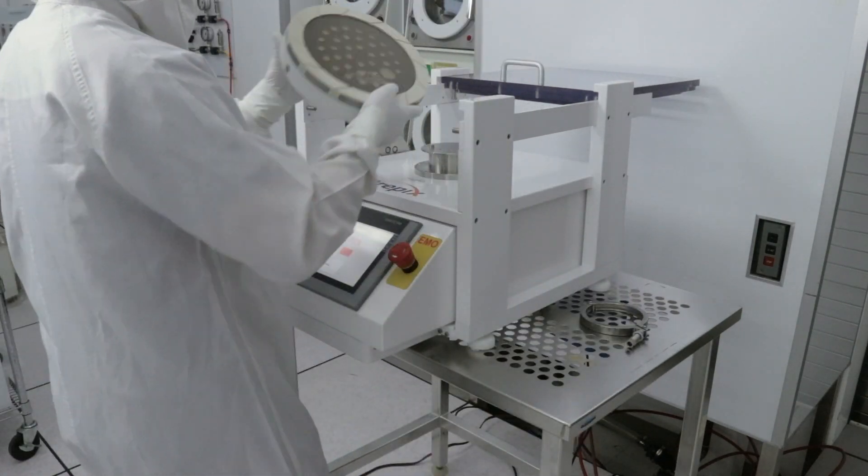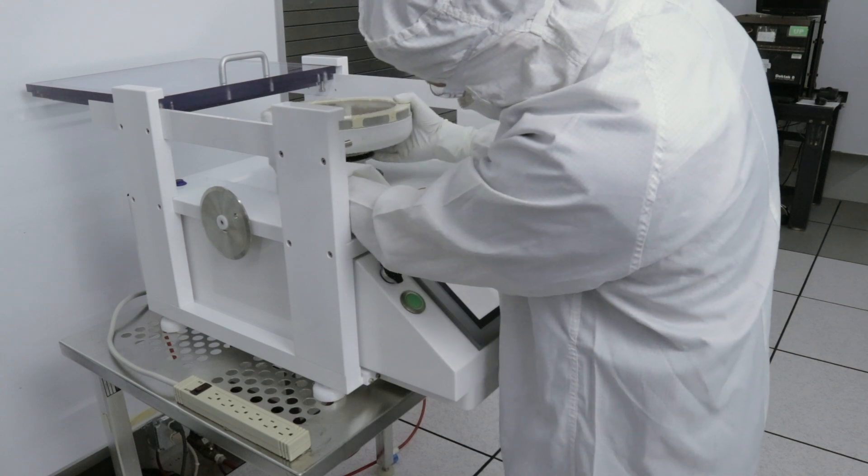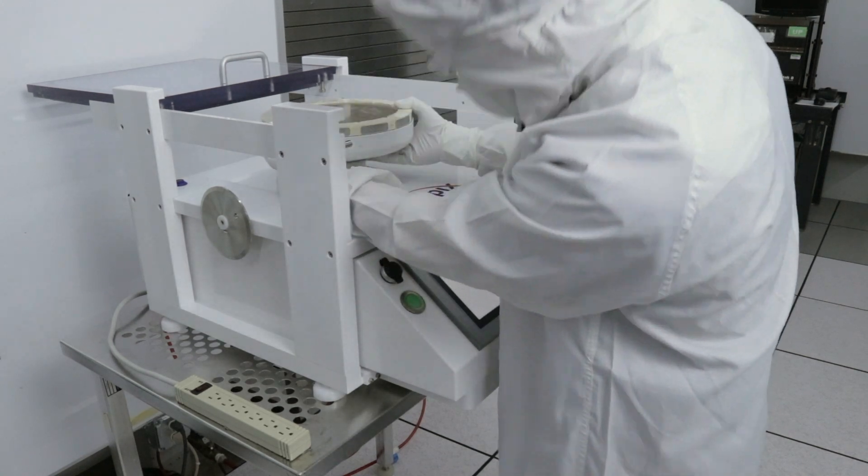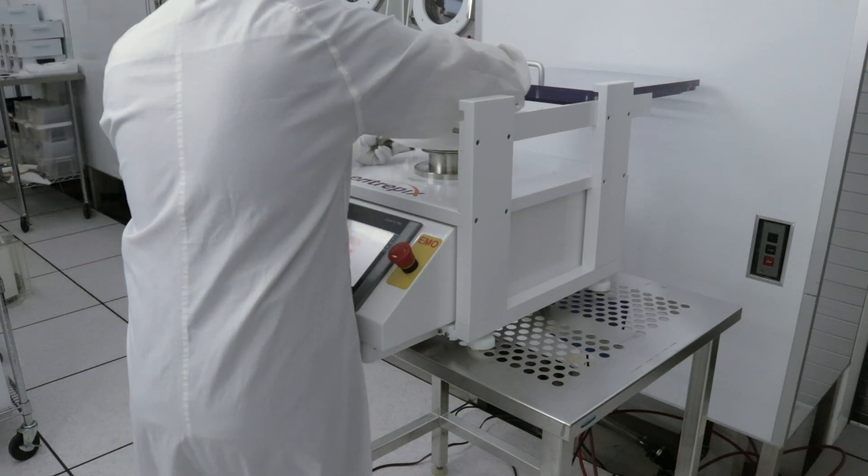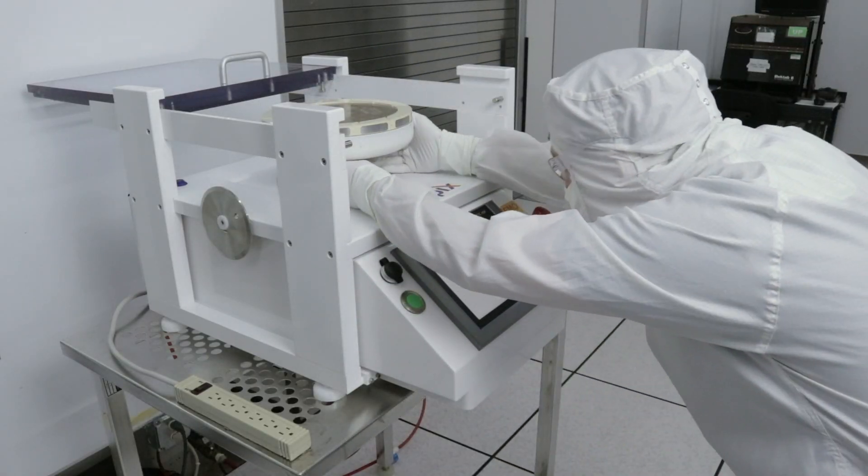Until now, testing of Titan, Profiler, and Contour Heads was limited by the capabilities of the legacy OEM Head Tester, which allowed users to check the pressure and vacuum integrity of each chamber, as well as check for leaks or crosstalk between chambers.